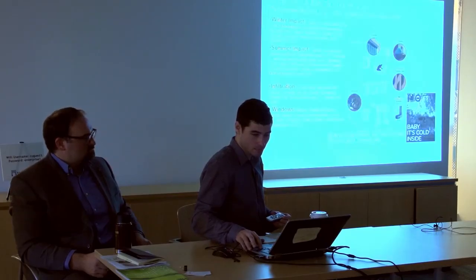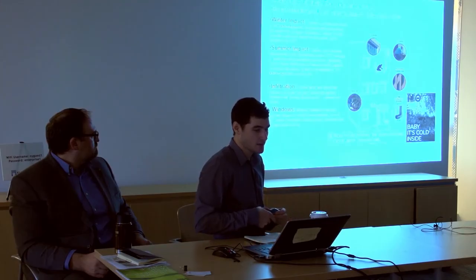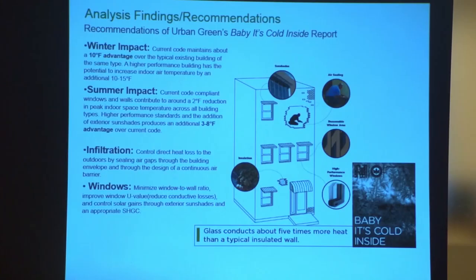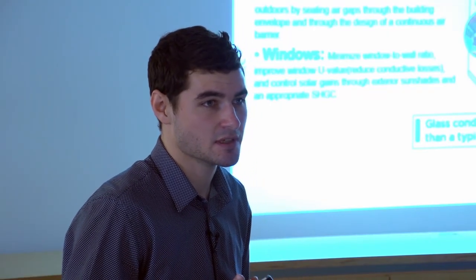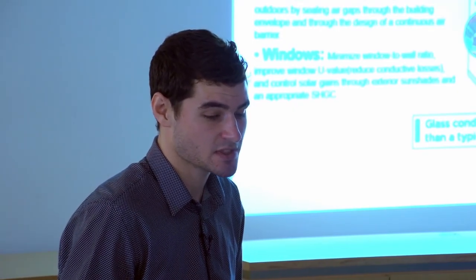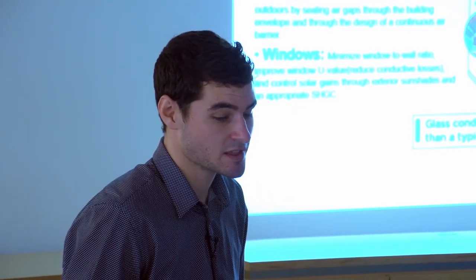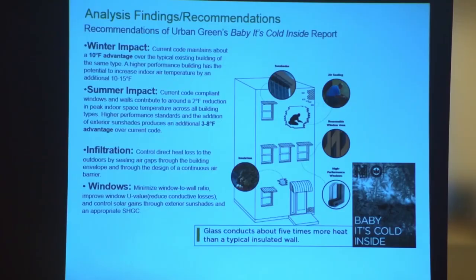So at this point, the results of this tool you'll find are matched very closely generally to some of the earlier research for Baby It's Cold Inside. And in summarizing in the winter, air infiltration or reducing air leakage through the facade and insulating the facade is very critical. In the summer, it's about shading the windows or selecting an appropriate glass with the right solar heat gain coefficient to minimize those solar gains.